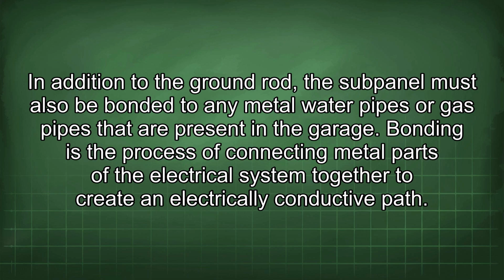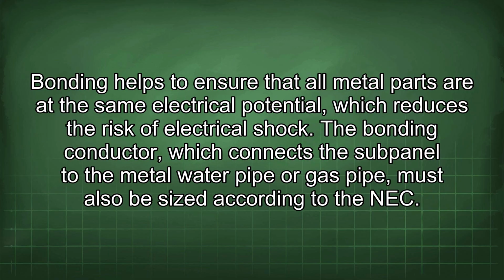In addition to the ground rod, the subpanel must also be bonded to any metal water pipes or gas pipes that are present in the garage. Bonding is the process of connecting metal parts of the electrical system together to create an electrically conductive path. Bonding helps to ensure that all metal parts are at the same electrical potential, which reduces the risk of electrical shock.